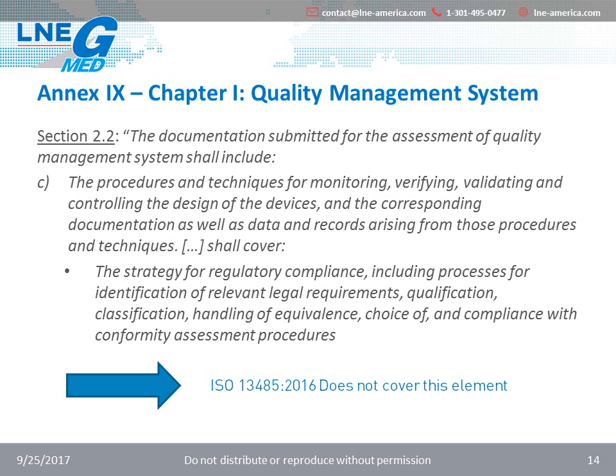So here again, when you are getting ready, you have your QMS, you have implemented your QMS, you believe everything is fine, just be sure that every single section of the IVDR is covered. Because even if the ISO 13485:2016 version is a very good base for your QMS, some elements might not be covered, and you need to be sure that these processes are included in it to answer the European regulation.